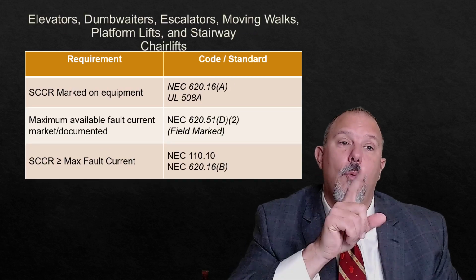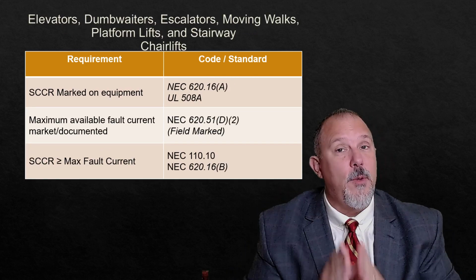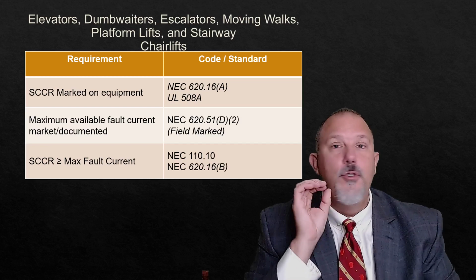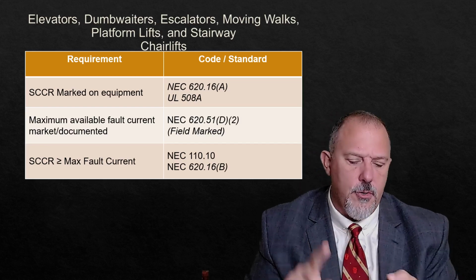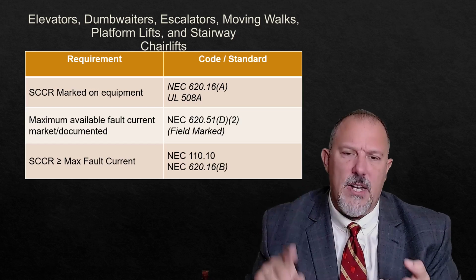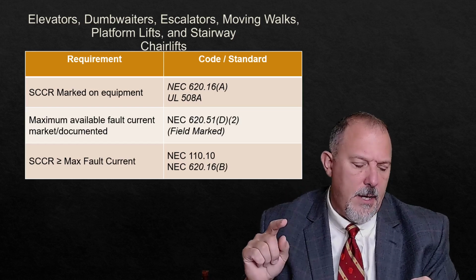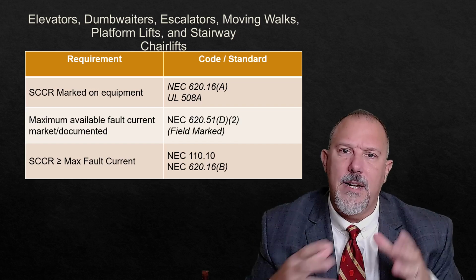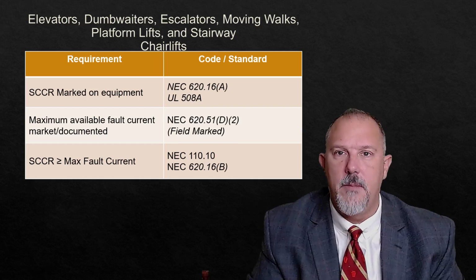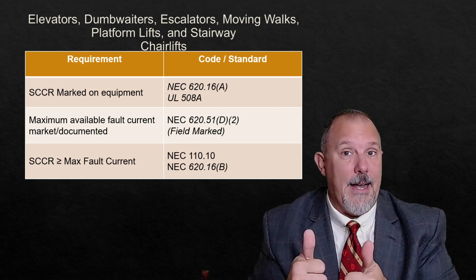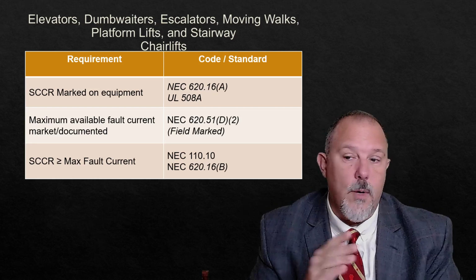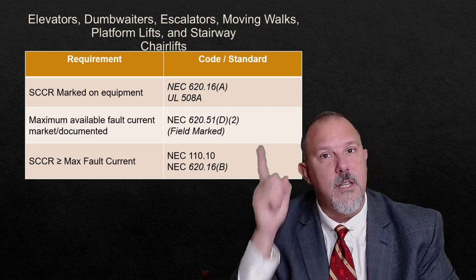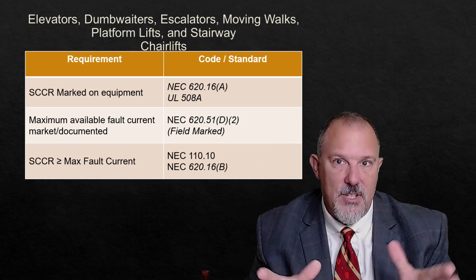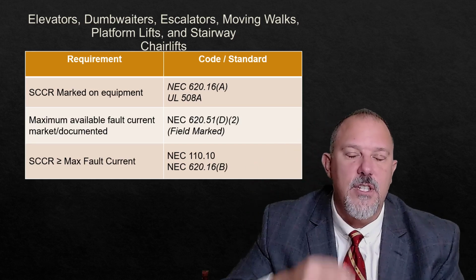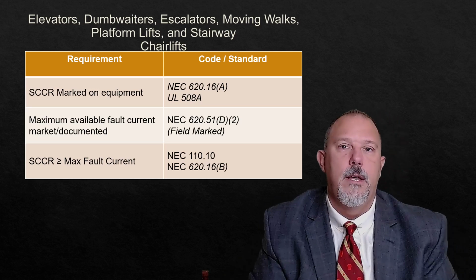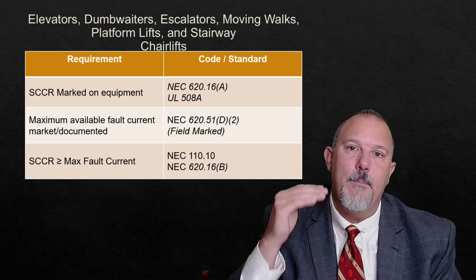And I'll tell you where one place for elevator control panels, especially where you've got to be mindful, is if you're in a downtown secondary network, like New York City, Seattle, Washington, Boston, Pittsburgh, Pennsylvania, any place where there's a secondary network in a downtown location, fault currents at the bottom of the building are typically very high. And in many of those tall buildings, what do they employ to get current from the bottom of the building to the top? They employ a busway. You know what a busway is? A high efficiency fault deliverable system. The fault current at the top of that building can be quite high.